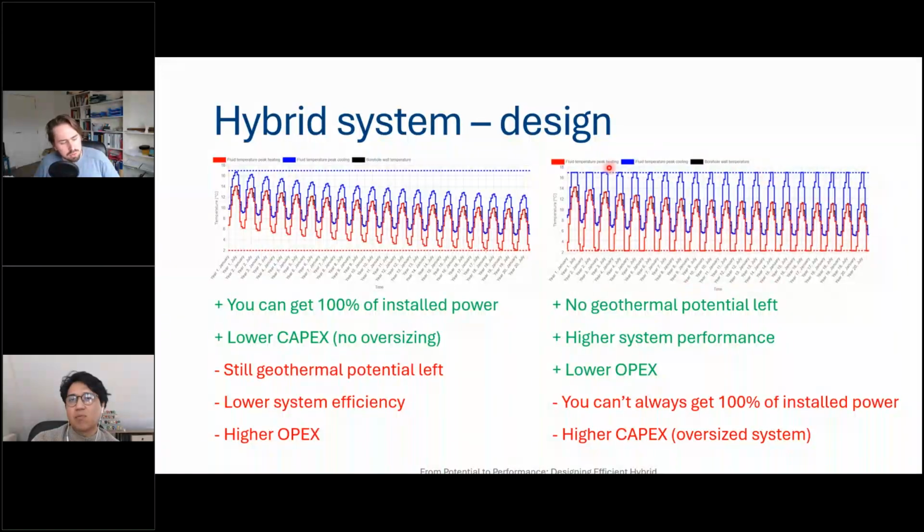If you have a very bad control strategy with the figure on the right, optimized for power, where you have 500 kilowatts, you can indeed cool down the ground way faster because you have that power. So you need a control strategy in order to make sure that you do not cool down the ground too much. But it really comes down to how you control it in practice and not so much on how you design it. Yeah. So I guess it's not a matter of the scenario, but rather the control system that you have. Yeah, indeed.